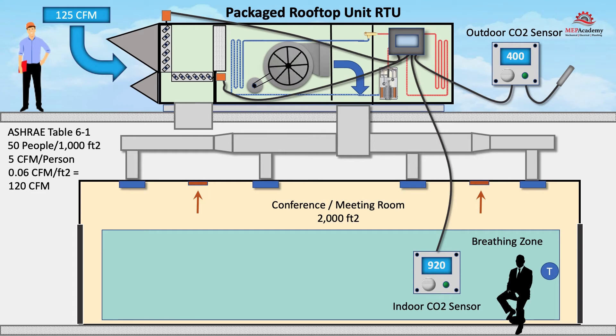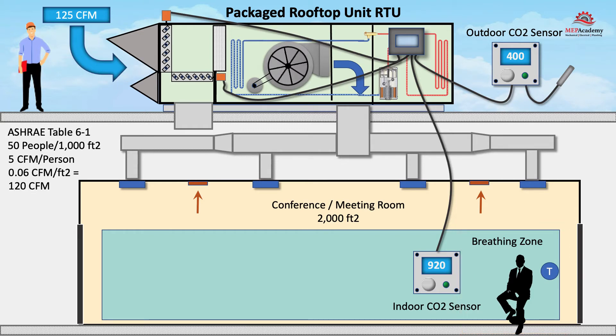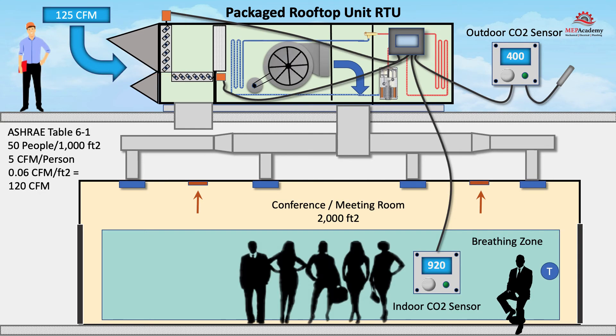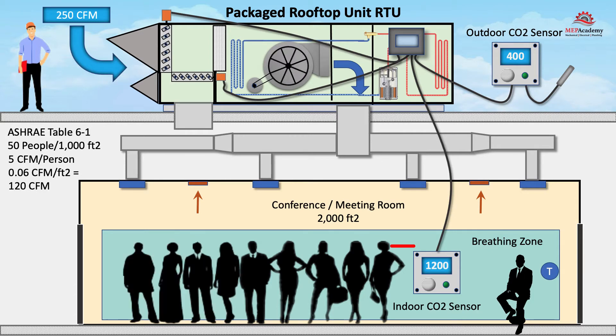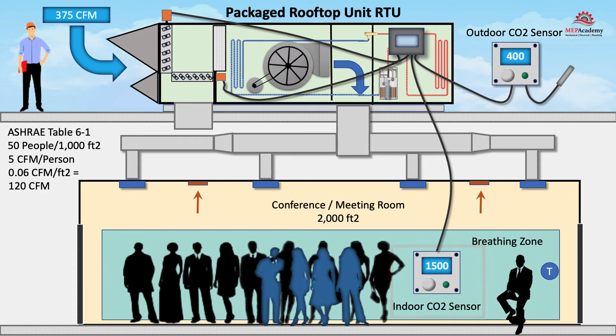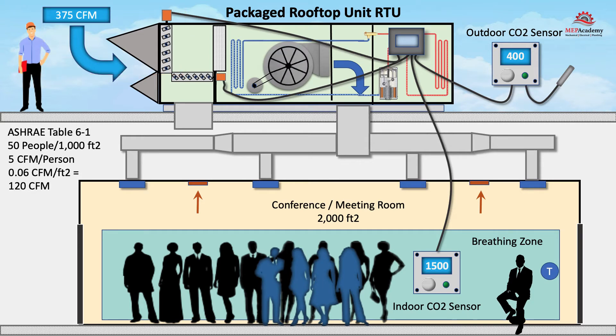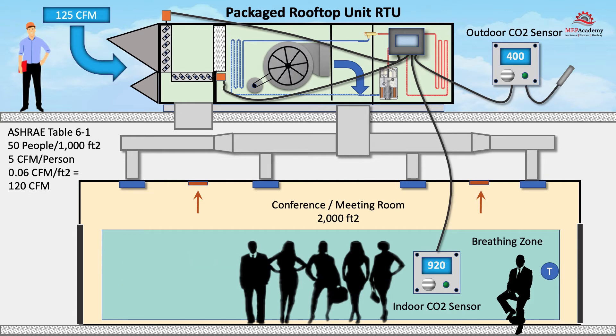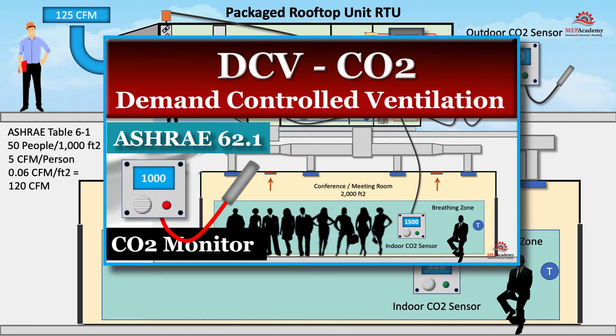Using a conference room as an example: if the meeting room was designed for 100 people, but only the presenter is currently in the room, the CO2 monitor would pick up the low quantity of carbon dioxide and close the outside air damper to match the occupant level. As more attendees arrive, the level of CO2 increases, the CO2 monitor picks up this increase and sends a command for the outside air damper to open wider, allowing more outside air into the space. As occupants leave, the system will begin to close the outside air damper. For a further explanation, see our video on demand controlled ventilation.